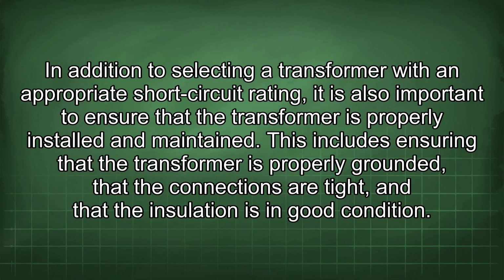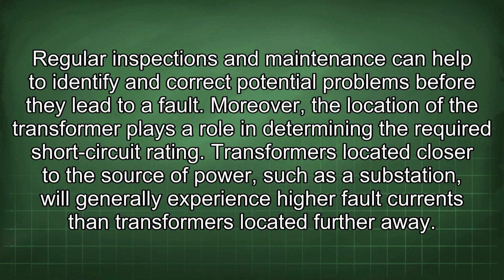In addition to selecting a transformer with an appropriate short-circuit rating, it is also important to ensure that the transformer is properly installed and maintained. This includes ensuring that the transformer is properly grounded, that the connections are tight, and that the insulation is in good condition. Regular inspections and maintenance can help to identify and correct potential problems before they lead to a fault.